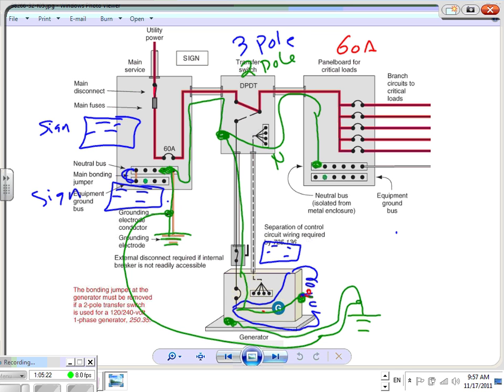Any questions, guys? The second thing I want to bring to your attention is this conduit. Can you guys see this conduit? This is for control signals. So if you have your generator outside, I have to have a power conduit coming to the disconnect right next to another PVC conduit carrying the control wires. Control wires, for the most part, guys, are only there if you have an auto transfer switch. This one is an auto transfer switch.